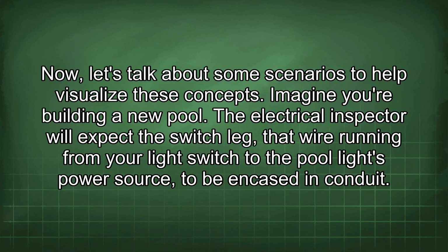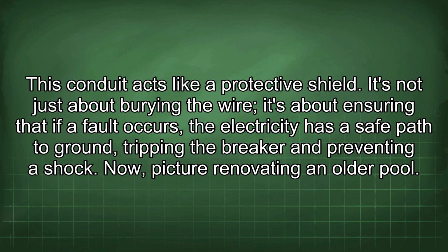Now let's talk about some scenarios to help visualize these concepts. Imagine you're building a new pool. The electrical inspector will expect the switch leg, that wire running from your light switch to the pool light's power source, to be encased in conduit. This conduit acts like a protective shield. It's not just about burying the wire, it's about ensuring that if a fault occurs, the electricity has a safe path to ground, tripping the breaker and preventing a shock.